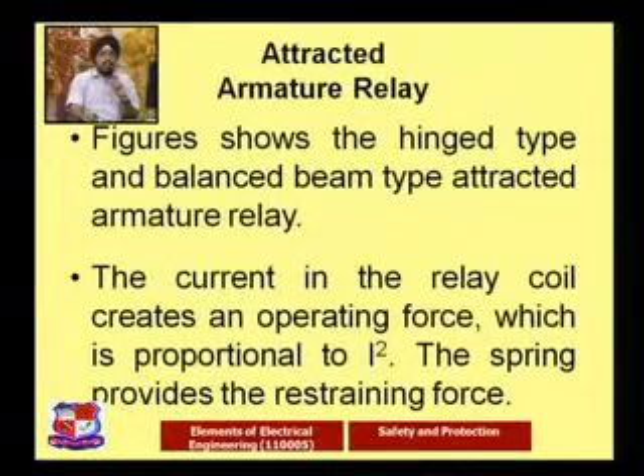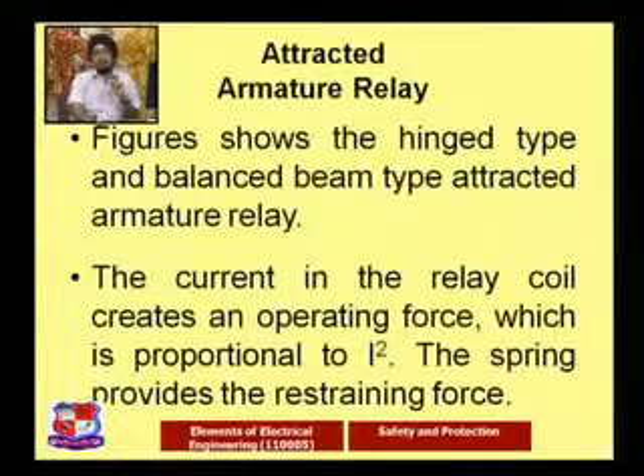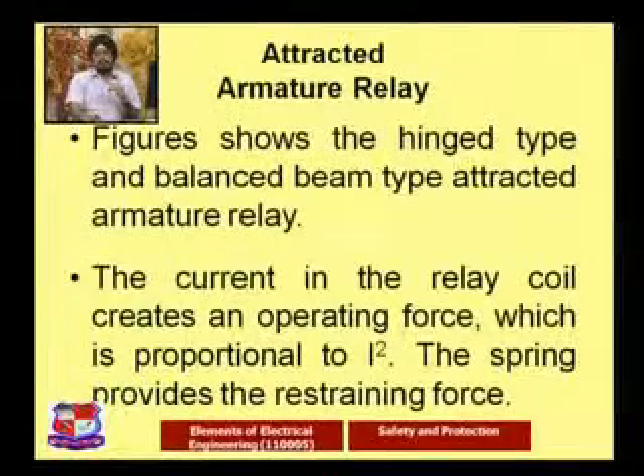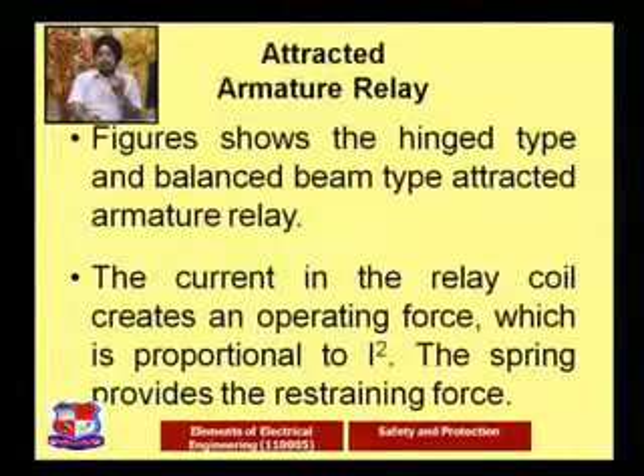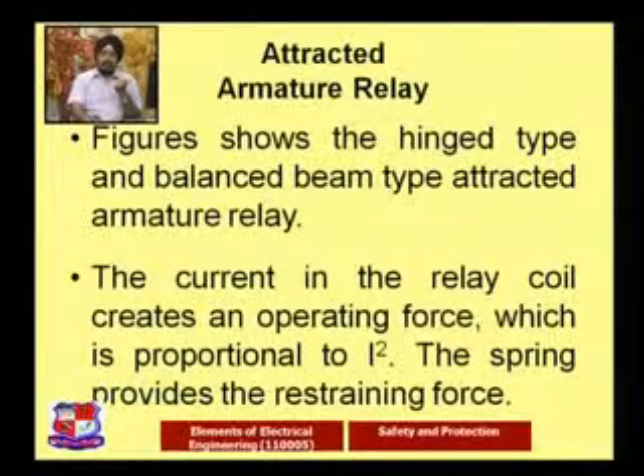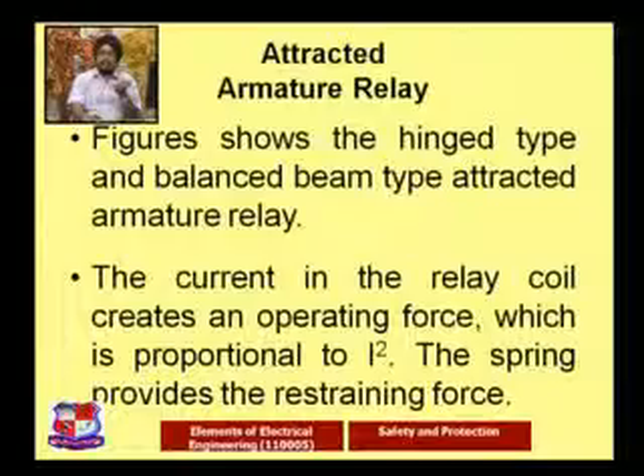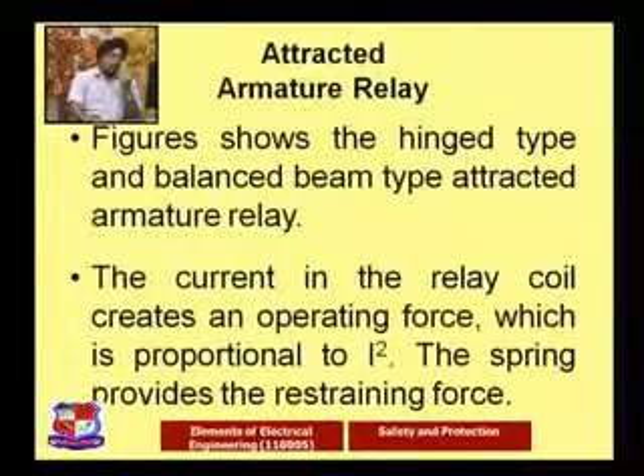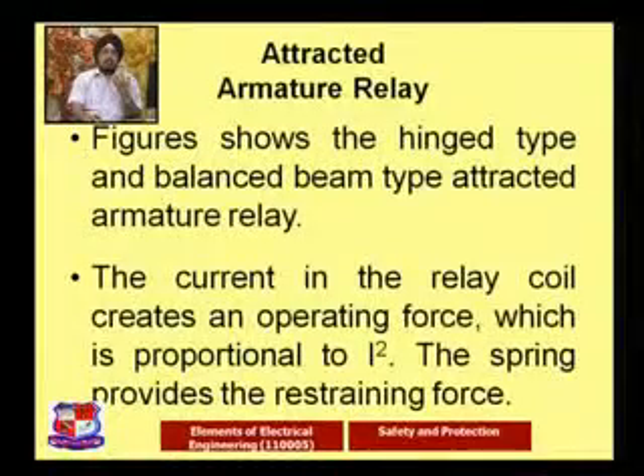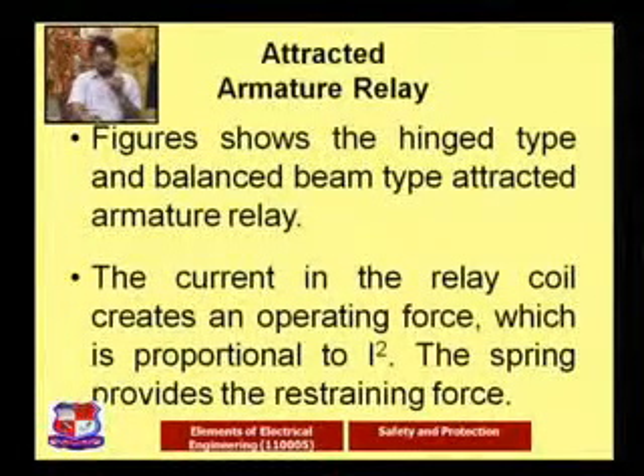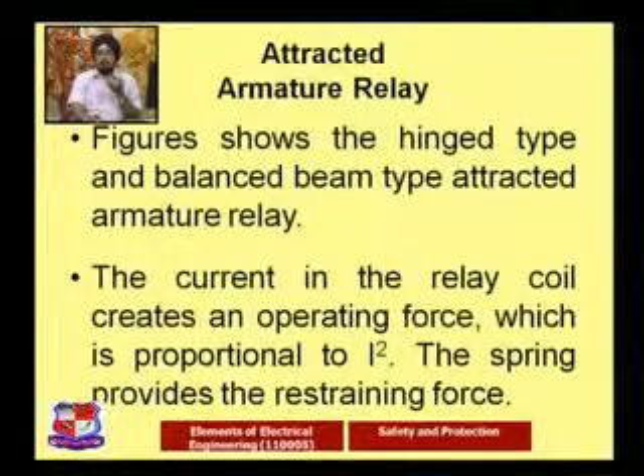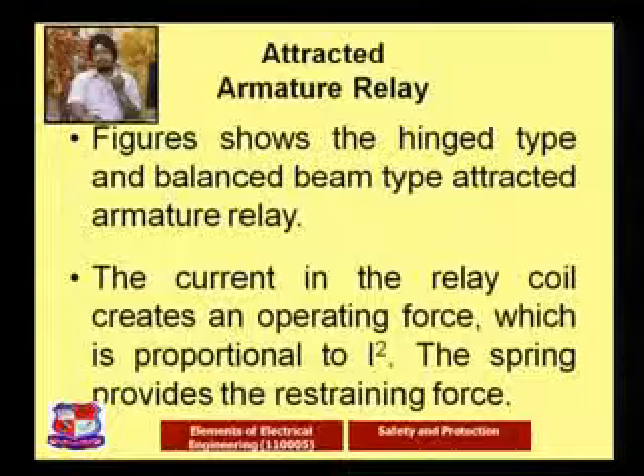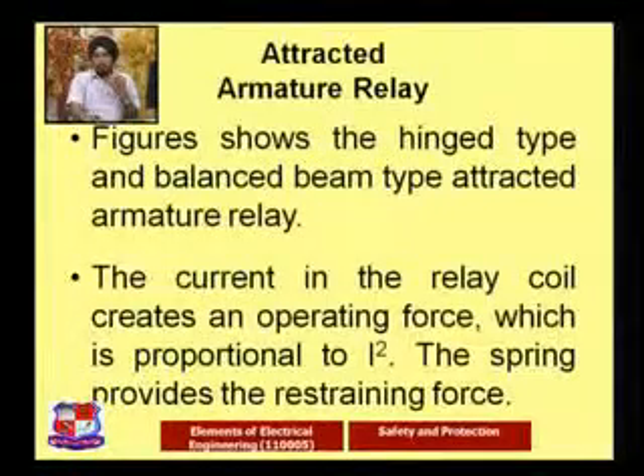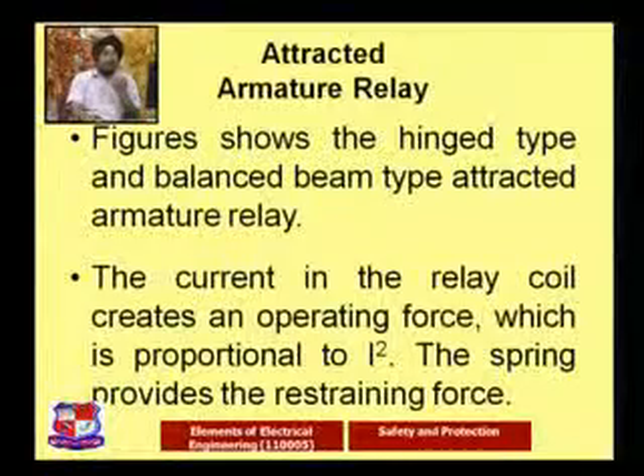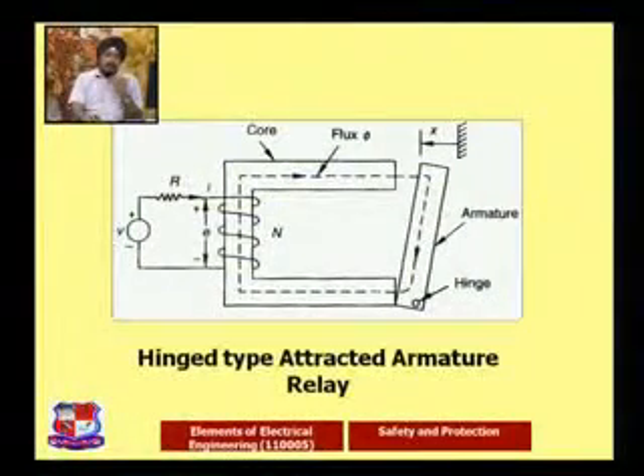Let's go with the first one, the attracted armature type relay. Now there are two types of that relay: one is the hinge type relay and one is the balanced beam type attracted armature relay. As the name indicates, in both cases the armature is attracted when there is a flow of abnormal current. The current in the relay coil creates an operating force. Whenever current flows into the coil of the relay, it creates the operating force. That force is proportional to the square of the current flowing in the circuit. At the same time, a spring is provided for the restraining force.